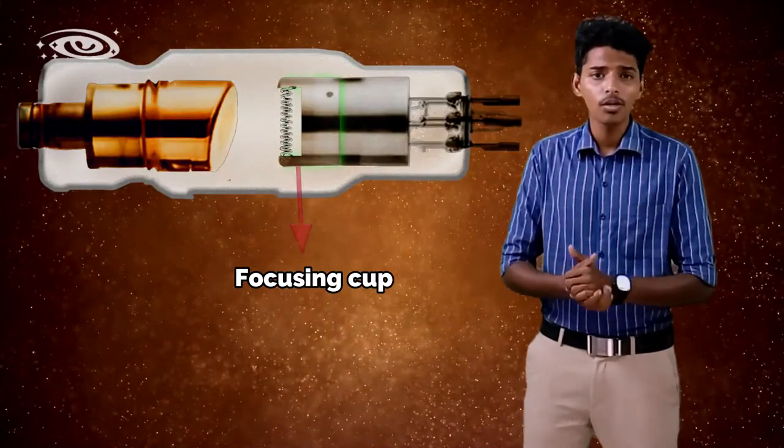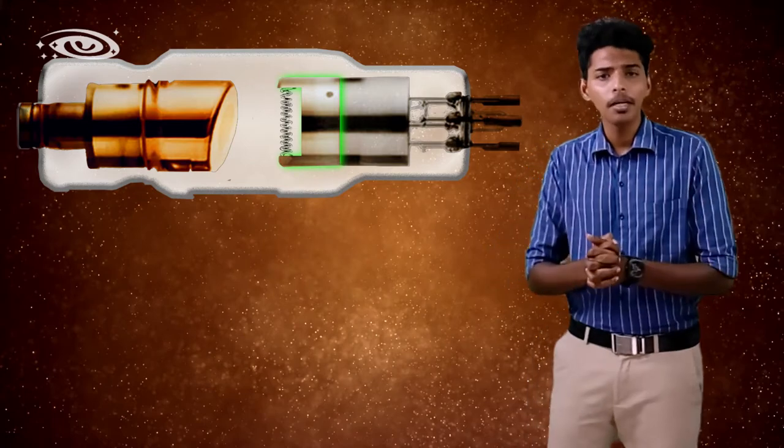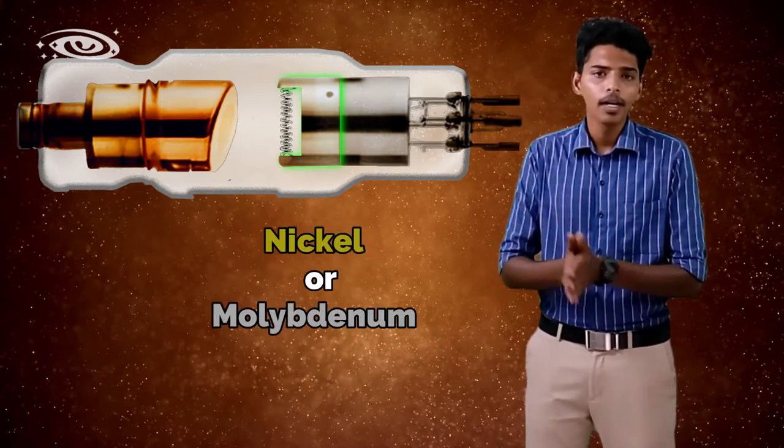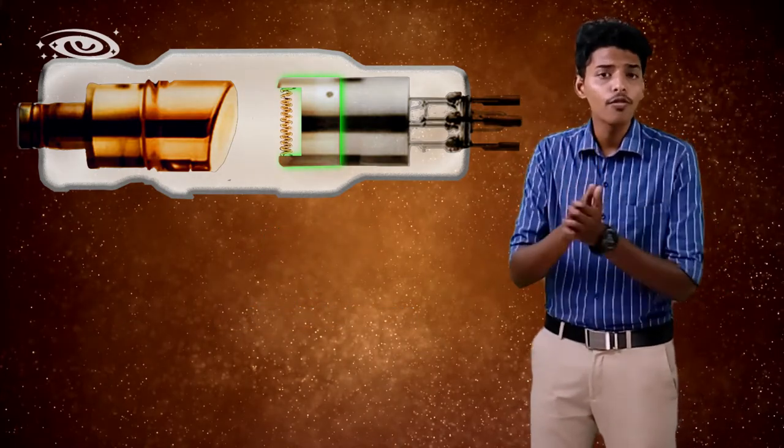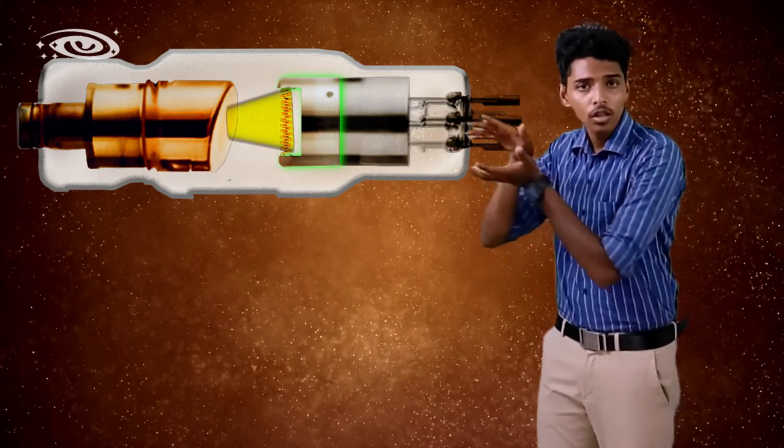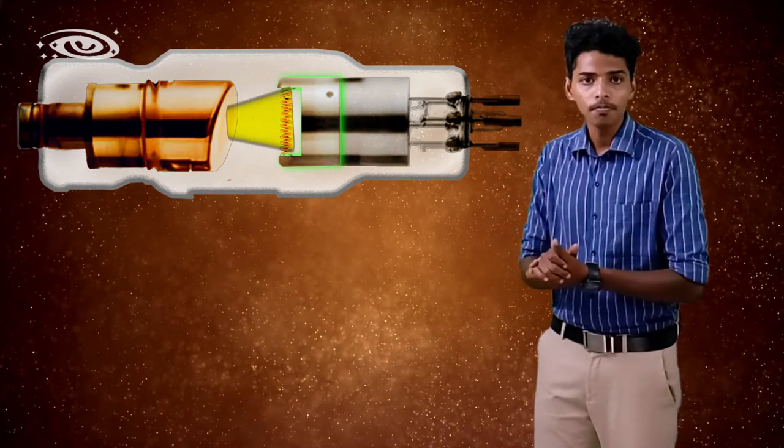Now we'll see about the focusing cup. This focusing cup is made up of nickel or molybdenum. The reason for using the focusing cup is to focus the filament electrons to the focal spot of the anode.